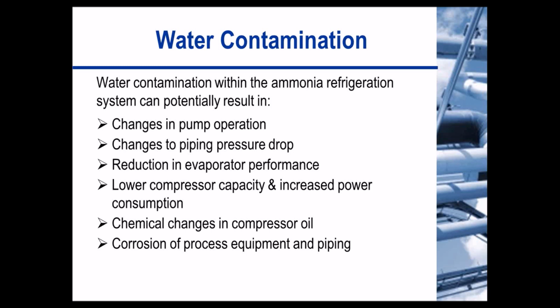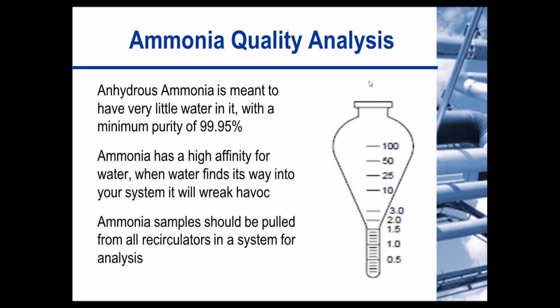Because of this, ammonia quality analysis is an important part of your non-destructive testing program. Anhydrous ammonia is meant to have very little water in it, and is actually supposed to have a purity of 99.995%. Ammonia has a high affinity for water, so when water finds its way into your system, it will wreak havoc on it. One place ammonia samples should be pulled from is the recirculators in your system. Once you have water in your system, be aware it never leaves. It's just going to gather in cold points within the system due to its lower vapor pressure relative to ammonia.